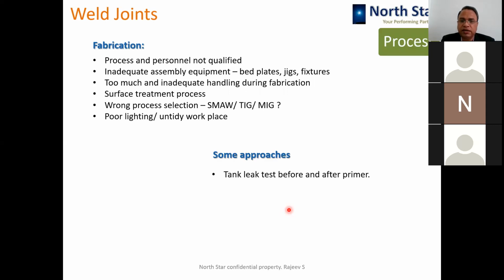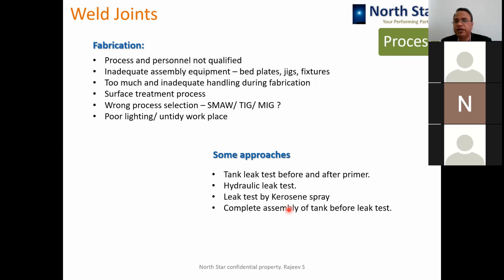Leak testing before and after primer is a good approach to prevent tank leakage. Hydraulic leak testing, done by one or two tank manufacturers in India, is very effective at identifying leakages. Some people spray kerosene to identify minute leakages from welding joints.